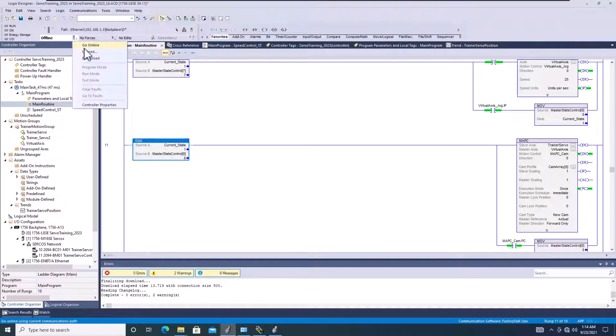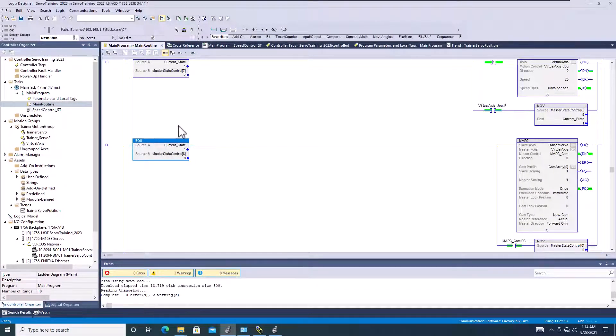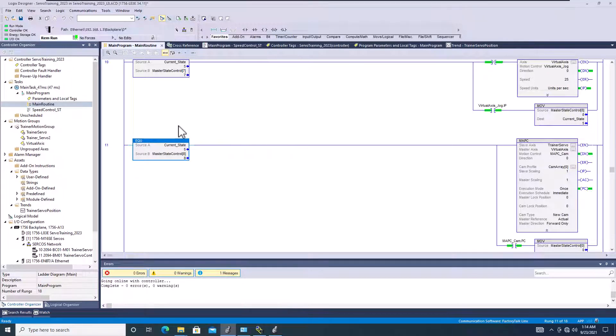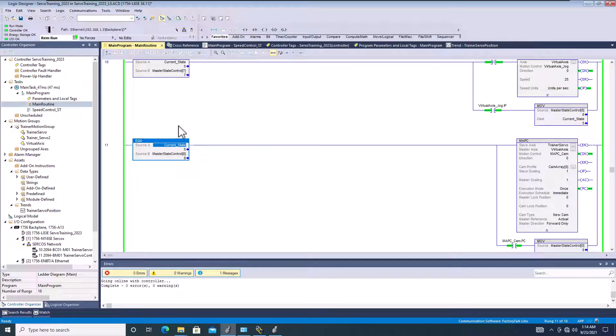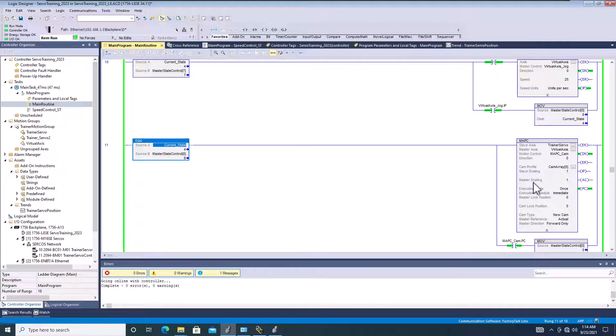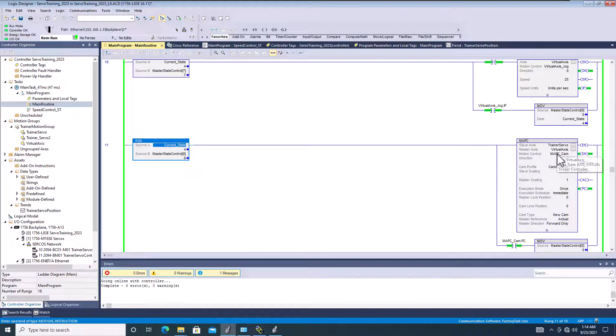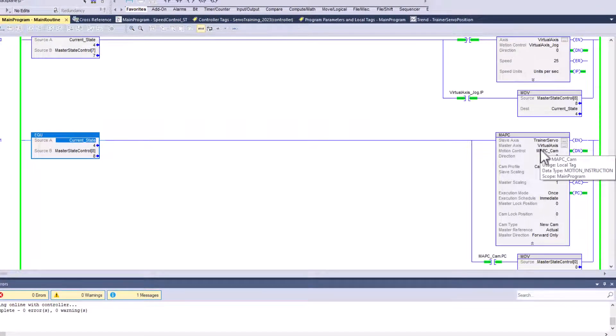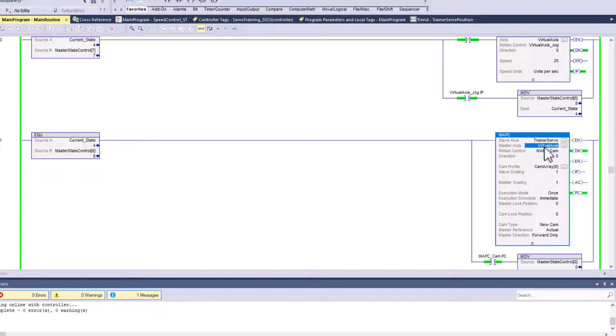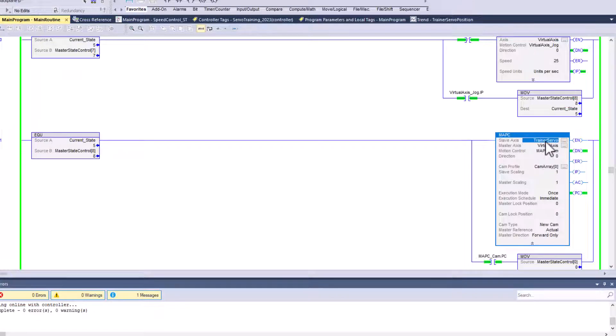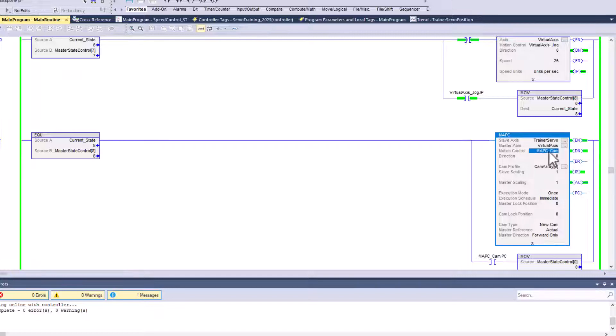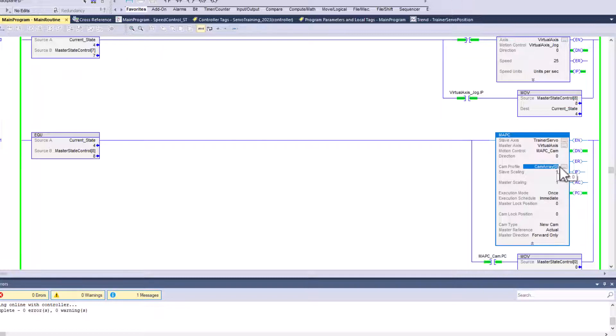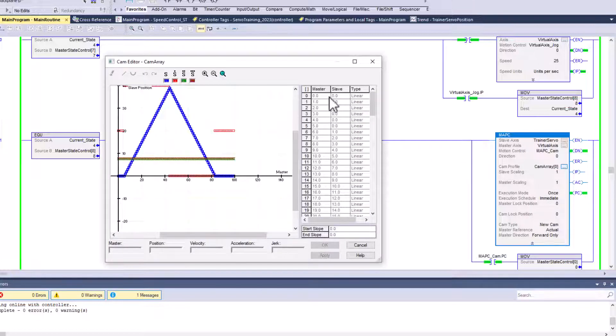Again, to not stretch this video out any longer than it has been, to get out of that Motion Axis Position Cam error of 13 and extended error of 10, verify that you are working within your tolerances of that actual servo, the two servos that are working together, meaning in this case my virtual axis and my actual servo that I'm controlling with the slave axis. Again, when it comes down to it, make sure your array is within the values, meaning you're starting with zero and you do have a good range inside of here.